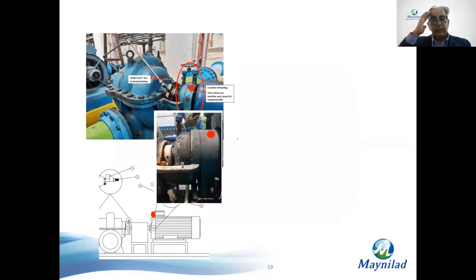This is an example of some sensors. For instance, we placed vibration sensors on motor pump assemblies. This can give a lot of information, especially for preventive maintenance—if there's certain vibration occurring, you can preempt the equipment from breaking and take action. By putting many different vibration sensors in different axes, you can see what the problem is: is the equipment not well anchored, is it not aligned, is it lacking lubrication, or is the bearing about to break? You can do a complex analysis.